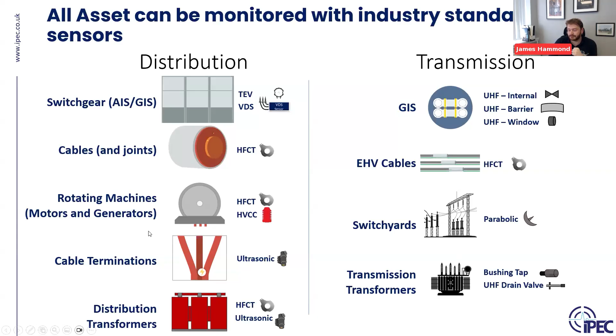So why actually carry out PD testing? One thing is condition-based maintenance. The market's shifting, rightly so, moving away from time-based testing or time-based maintenance, just going 'this asset is 10 years old, it needs to be tested.' Everything's trying to be more optimized and streamlined, and keep reducing costs, and this is one way to do it. Getting that real-time asset condition and knowing there's a problem based on the condition itself is much better than just waiting for a certain length of time to pass, because then maybe you find an asset that's new but has PD needs more attention than an old asset that doesn't have PD.